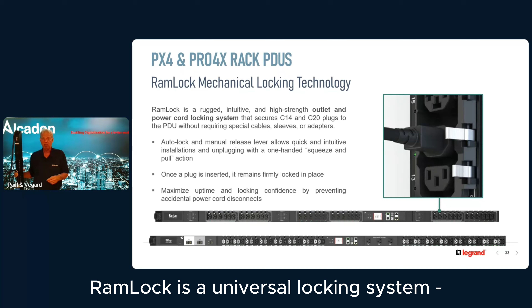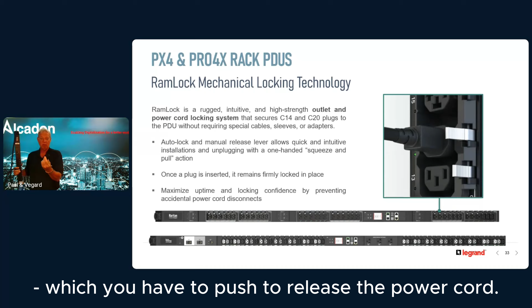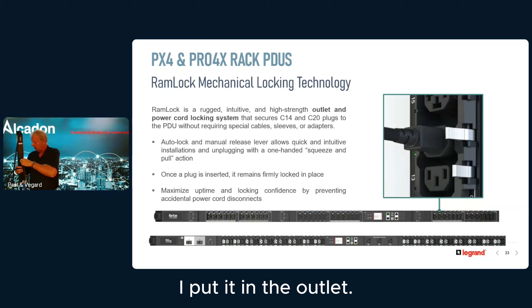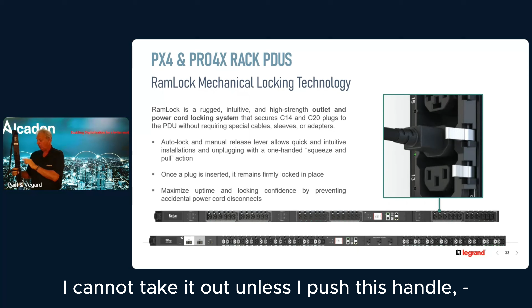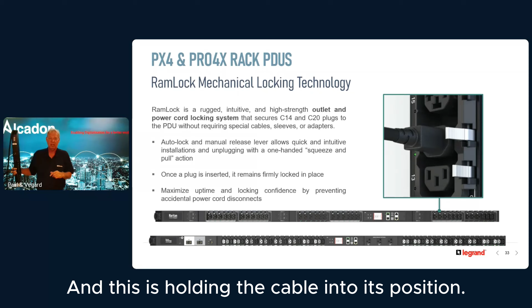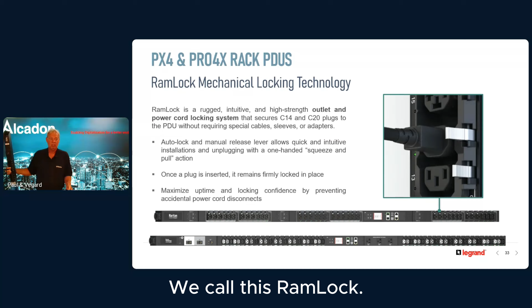We've also introduced Ramlock, a universal locking system that works with all C19/C20 and C13/C14 power cords. It's a handle on the side of the outlet that you push to release the power cord. With a standard connector, once I put it in the outlet I can't take it out unless I push this handle. One of the biggest issues in data centers is cables getting loose, and this holds the cable in position. We call this Ramlock.